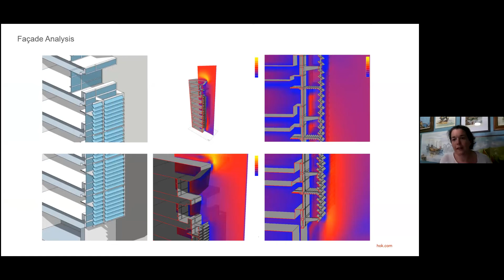Here we have chill beams. We ended up going with a chill beam system because of the 100% outside air requirement. This reduced floor to floor height, which was one of the trade-offs that helped with cost mitigation, so we didn't have to pay for as much enclosure material. You can actually see those right here—these are active chill beams—and you can also see that perimeter circulation zone.